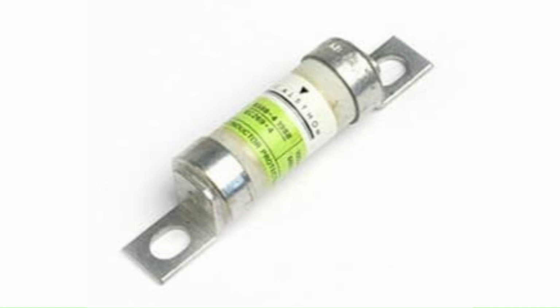HRC fuse has high speed operation and also does not require maintenance. But the fuse element of the HRC fuse needs to be replaced after each operation. And it also produces heat during the faults, which will affect the operation of the nearby switches. The enclosure of the HRC fuse is filled with powdered pure quartz, which acts as an arc extinguishing medium.